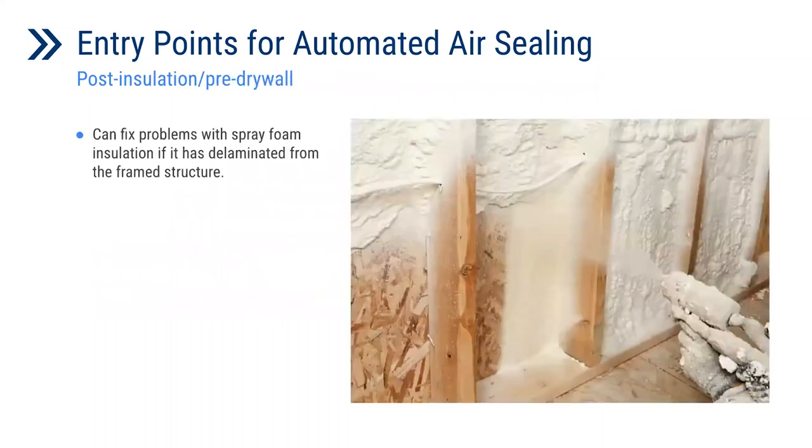For post-insulation, pre-drywall, if there are any issues with the spray foam insulation, this is another opportunity to come through and perform that process. In the case of Building 40, the contractor had previously applied the spray foam insulation. We had a relatively airtight building, as Emma Shaw showed, but we were still able to double the overall airtightness of the building as a result of the AeroSeal barrier sealing.